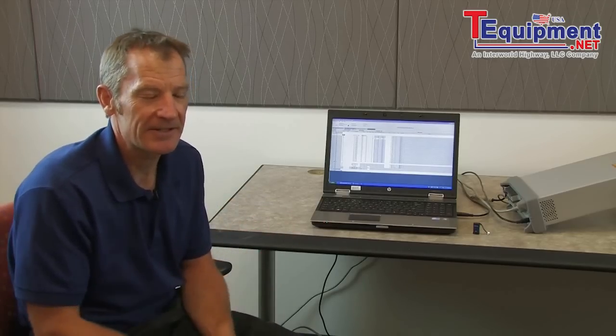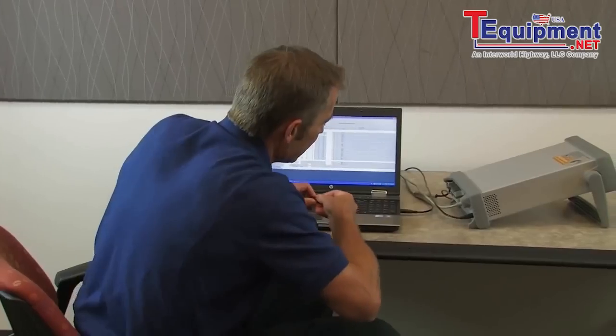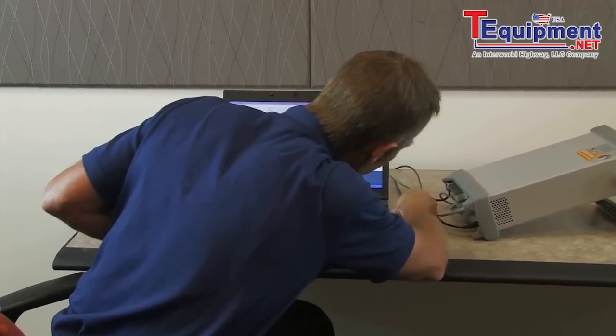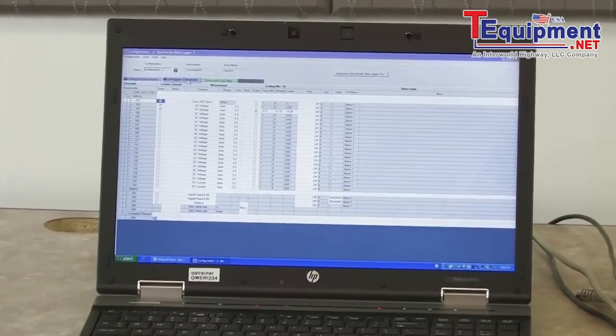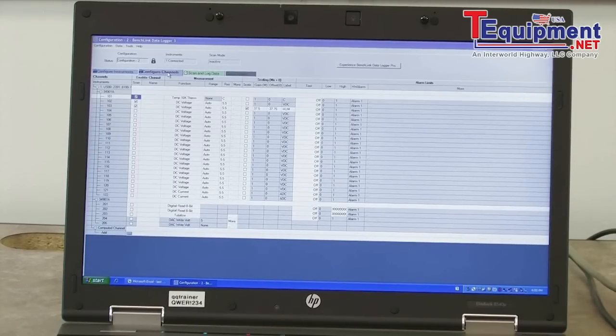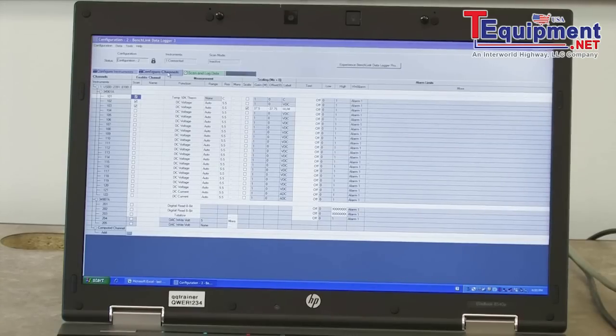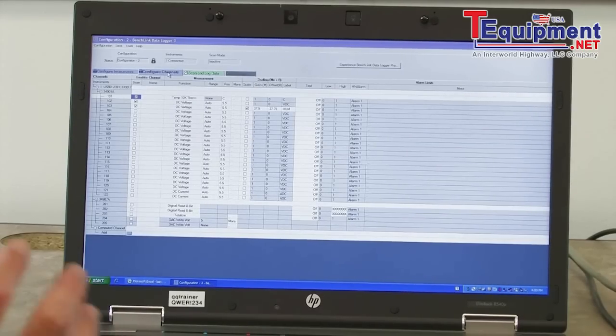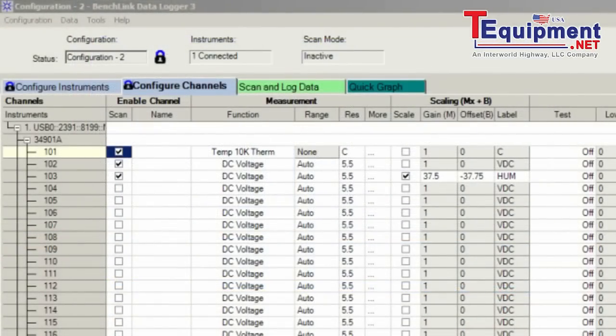The second method of USB data logging is to combine using the BenchLink DataLogger along with our USB stick. Let me go ahead and insert our USB stick. One of the really nice features of the BenchLink DataLogger software is it makes it easy to set up a lot of channels. So if you're using a lot of channels, it makes sense to use the BenchLink DataLogger software. And in the case of having the PC not near the instrument, using the USB stick can really help transfer that configuration over to the 34972.